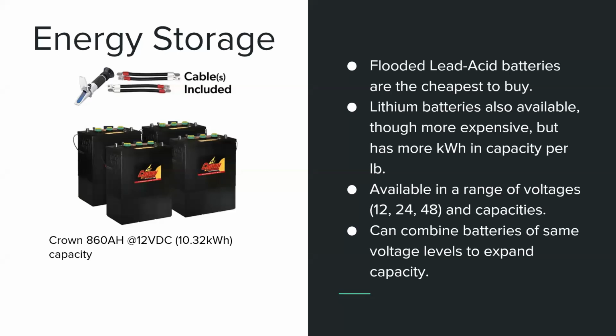They're the cheapest to buy, and they come in voltage ranges of 12, 24, 48. And you can combine batteries of the same voltage levels to expand your capacity. However, the flooded lead acid batteries weigh a ton. These 4 batteries alone, according to the specs, weigh approximately 600 pounds. So if you're putting it on a mobile unit, as we are, weight is a serious concern.